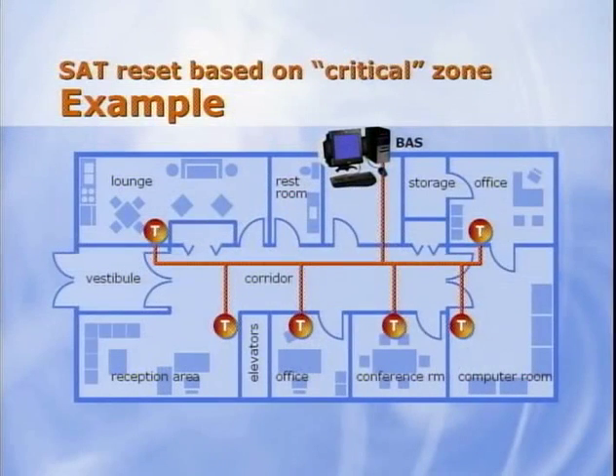Alternatively, some strategies reset the supply air set point based on the temperature in the critical zone. In this case, the critical zone is the one that is most at risk of overcooling, which would require activating local reheat. A building automation system monitors the temperatures in all the zones. The critical zone is the one with the temperature closest to its heating set point. Based on a signal from the BAS, the rooftop unit resets its supply air temperature set point to prevent the critical zone from needing reheat.